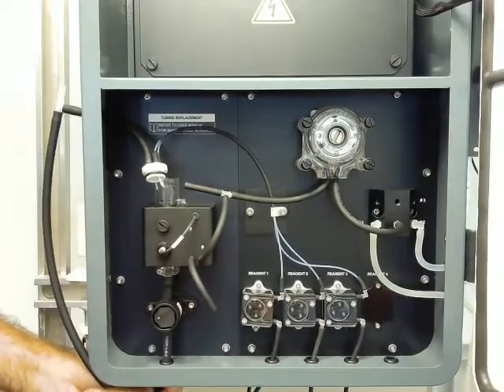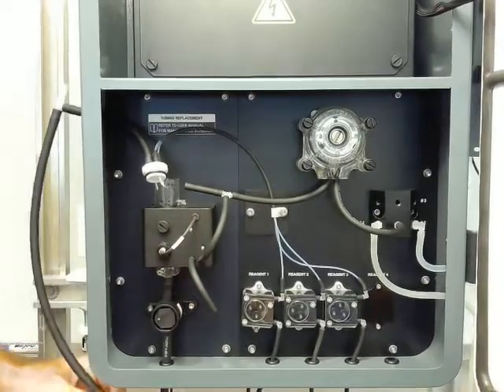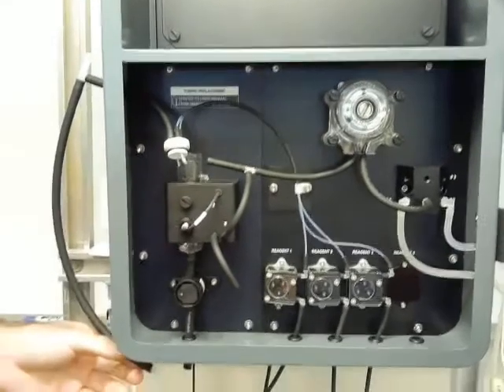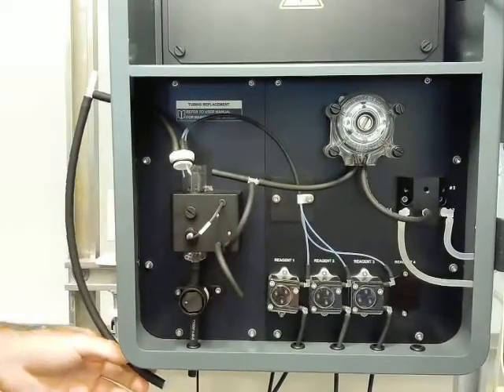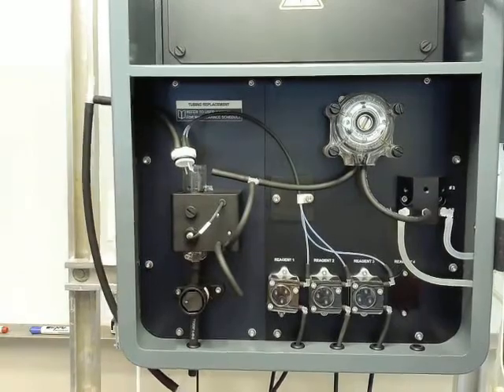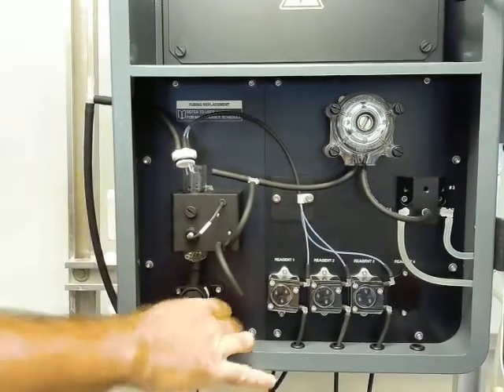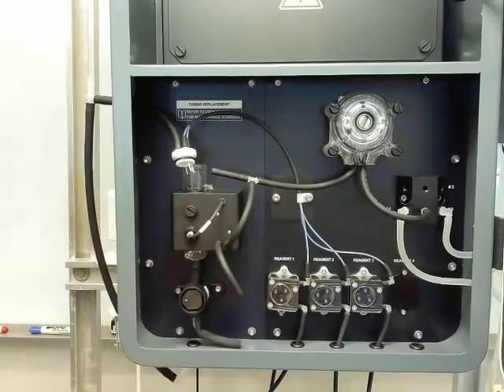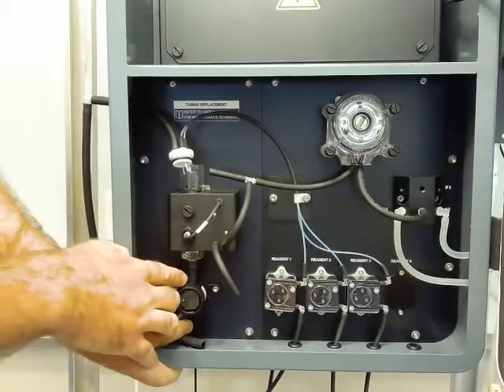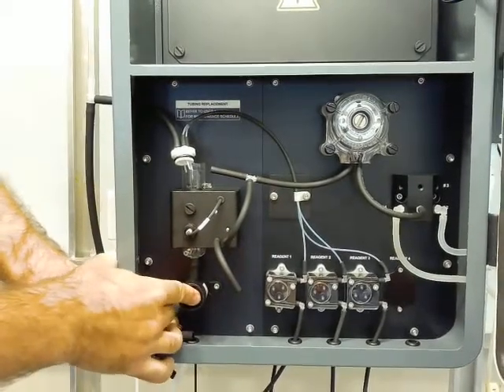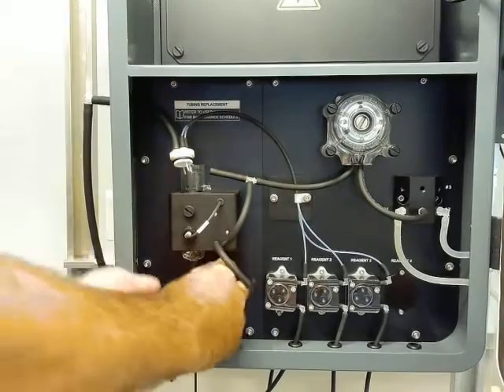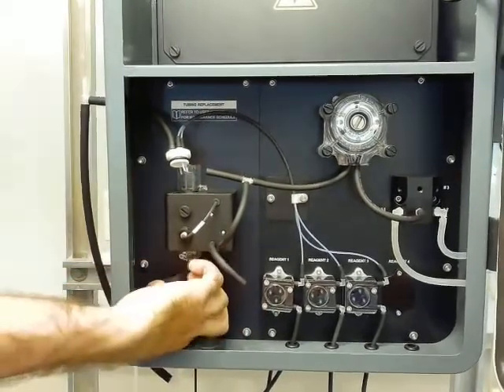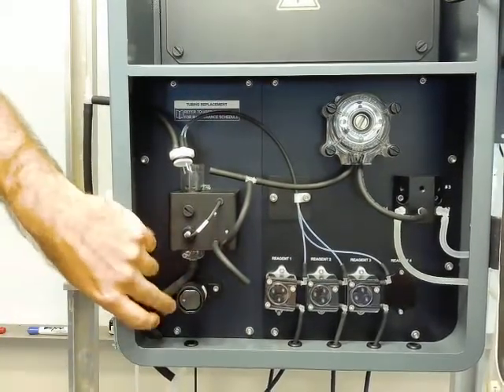So on the bottom of the analyzer is just a tube fitting, which is tied to the overflow drain vent. So we can pull the tubing up through the bottom of the analyzer, and then we just need to release it from this pinch valve. So in order to do that, we can just manually push in this valve, and then push our tubing out of the way and release it. So now we have our flow cell loose.